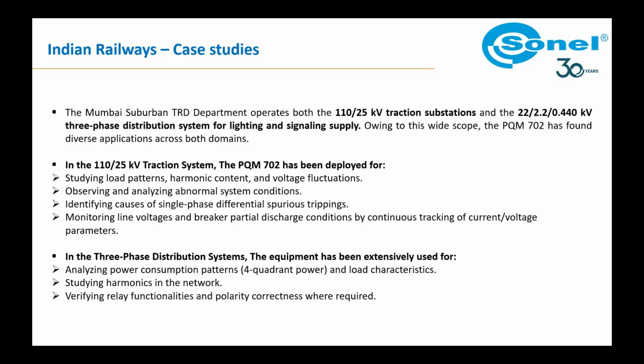For example, we have single phase transformers which we use for traction distribution. From a perspective view, we have single phase differential tripping which we have faced in our system. From the power quality meter, we can get current data even at the half cycle level. So we can closely monitor the current values and see the differential current arising from bad connections, bad contacts, and such use cases can be done with the PQM, along with the usual power quality measurements.